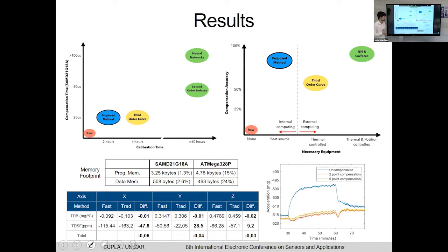The other main advantage of this technique is that it requires much less equipment. Only one heat source to offer a second temperature point other than the ambient temperature is needed, whereas other techniques require a thermally controlled environment or a thermally and position controlled environment. However, the accuracy of this compensation is similar to that of more complex techniques. We checked that the proposed algorithm can be run in 2 popular microcontrollers using only 3 to 5 kilobytes of program memory and around 500 bytes of data memory. Most of this data memory can be freed after the calibration.